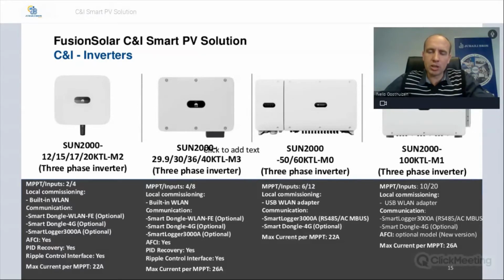Then the most popular inverter in this range is 100 kTL. Most of our EPCs in South Africa prefer the 100 kTL. It's got 10 MPPTs, which means you can have 20 strings to it. Local commissioning is via USB WLAN. Communication is the Smart Logger 3000A. The Smart Logger supports RS485 communication as well as AC Modbus. And then you can also attach a smart dongle, which gives you 4G communication.